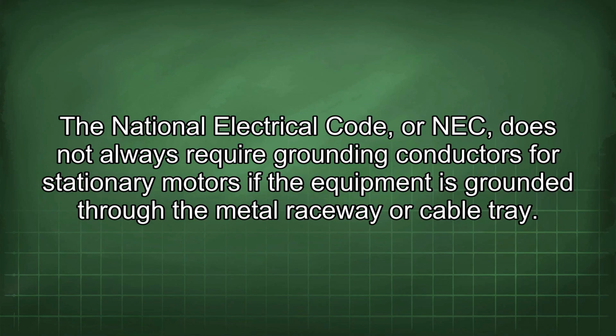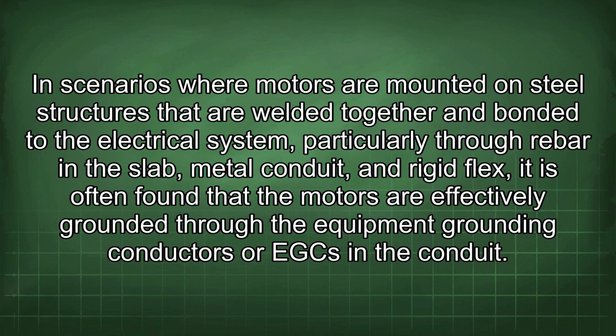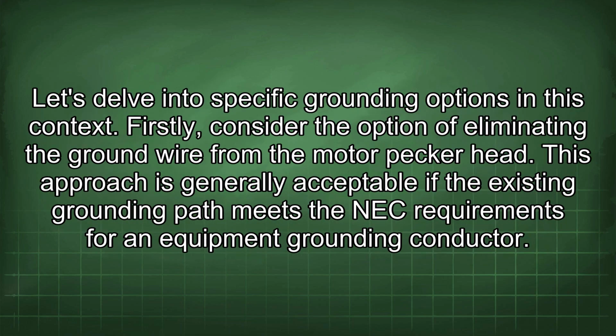The National Electrical Code, or NEC, does not always require grounding conductors for stationary motors if the equipment is grounded through the metal raceway or cable tray. In scenarios where motors are mounted on steel structures that are welded together and bonded to the electrical system, particularly through rigid metal conduit and rigid flex, it is often found that the motors are effectively grounded through the equipment grounding conductors, or EGC, in the conduit. Let's delve into specific grounding options in this context.